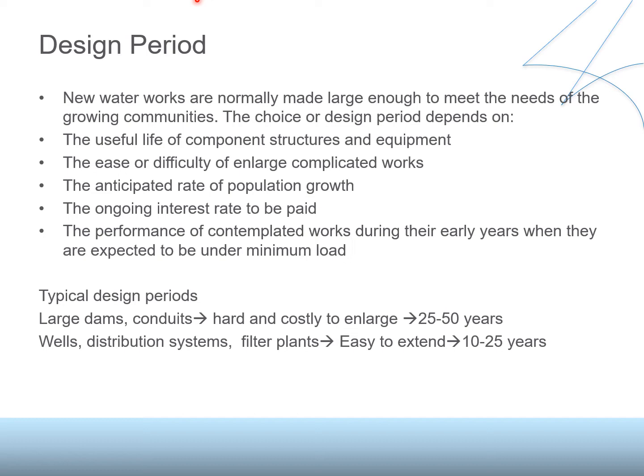There are several other factors to be considered when deciding design period, such as useful life of components and structures. If the majority of the components of the structure have a life of, let's say, only 20 years, then there is no point in designing the whole structure for 30 years. So the useful life of component structures and the equipment will decide what should be the right design period.